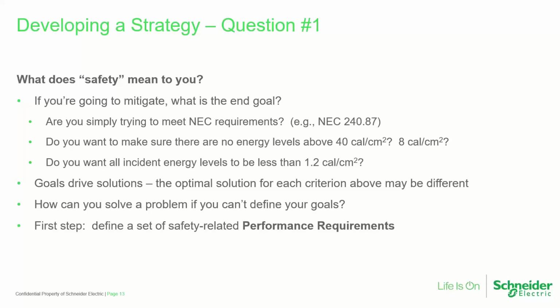One answer is that, okay, we just want a system that will comply with NEC requirements. And there are some NEC requirements around arc flash mitigation. Article 240.87, for example, that says you apply arc energy reduction methods if you have low voltage circuit breaker 1200 amps or larger. Okay, we can do that, maybe without addressing things farther down in the system. But that's not the only kind of answer that we've gotten to this. Sometimes customers want to make sure we don't have any incident energy locations above 40 calories per centimeter squared. You don't want it to say extreme danger on your labels or in your study or whatever, right? So let's bring it below 40.